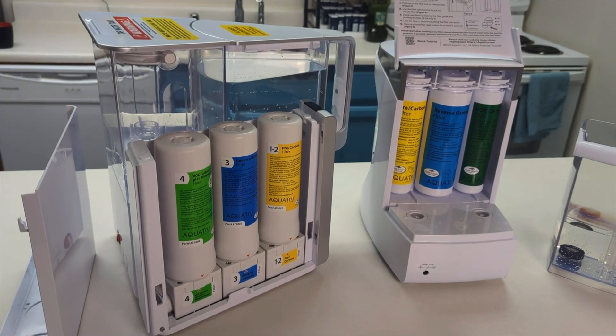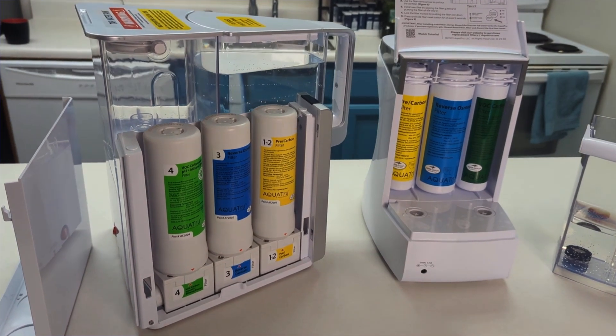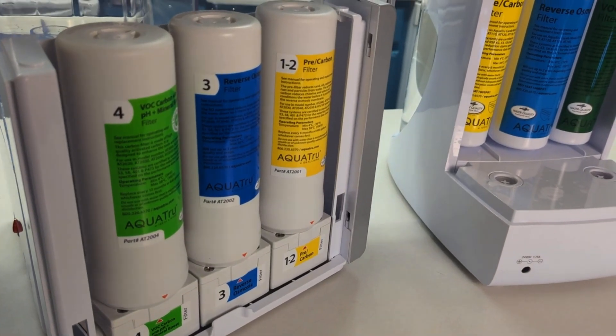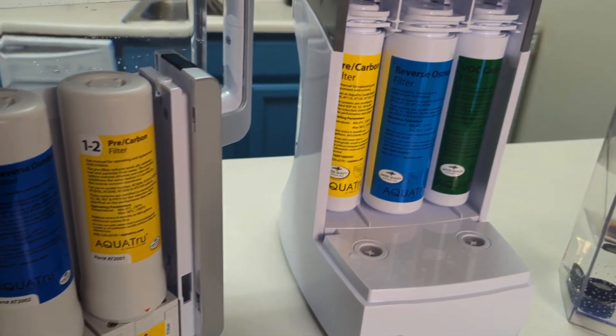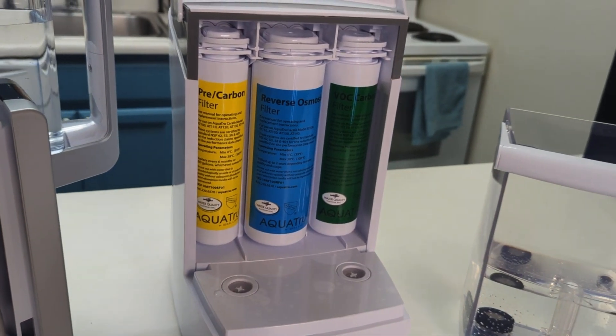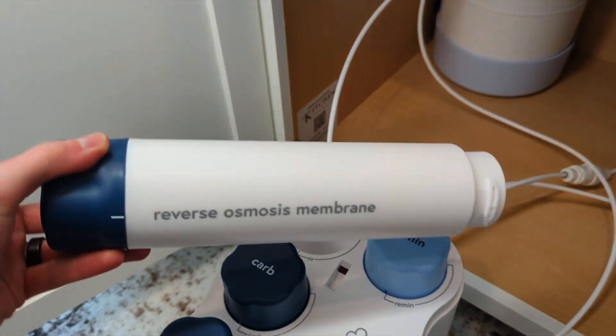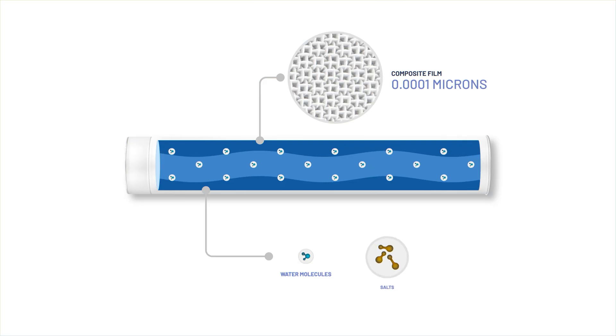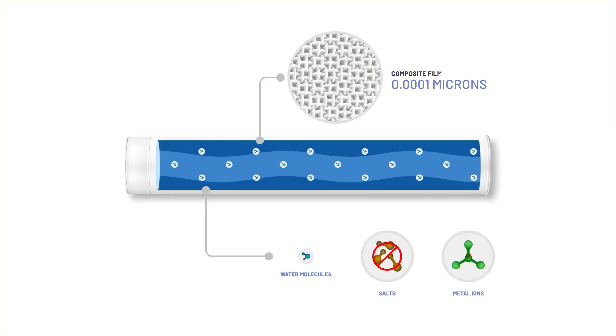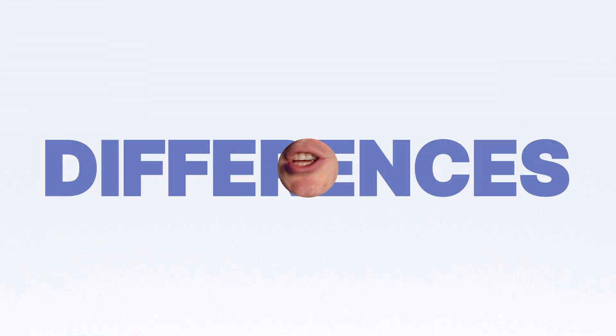Reverse osmosis takes this treatment a step further. It combines multiple filters like carbon and sediment filters with a semi-permeable membrane to remove up to 99.9% of total dissolved solids. Water is forced through the RO membrane under pressure, leaving behind contaminants which are then flushed away as wastewater.